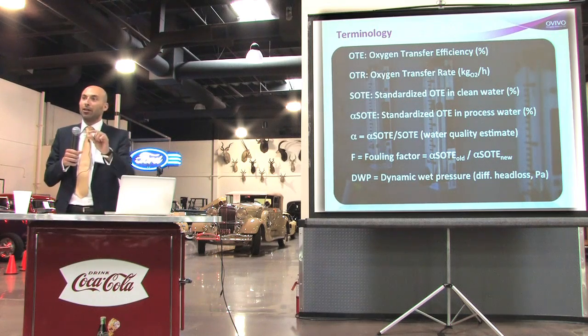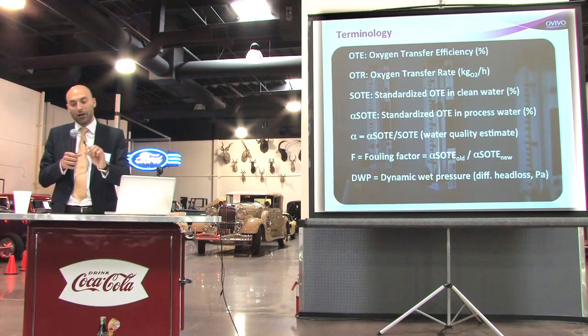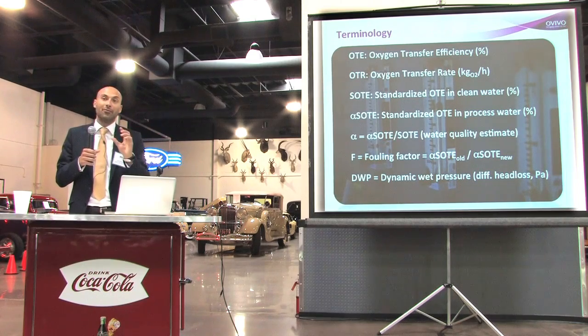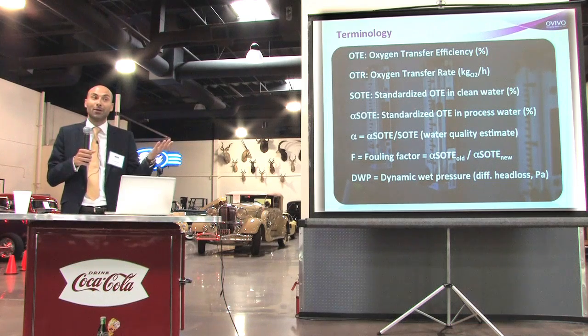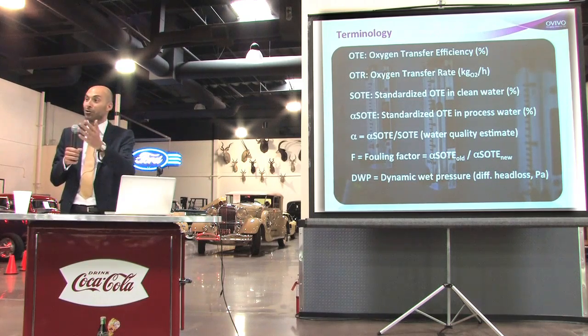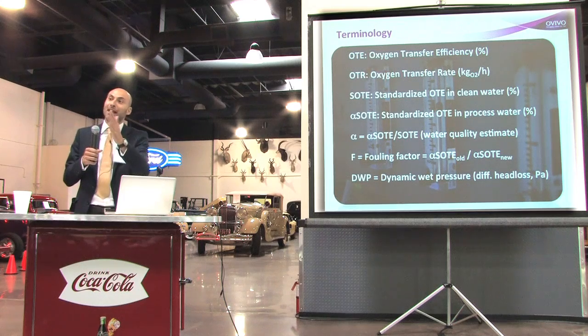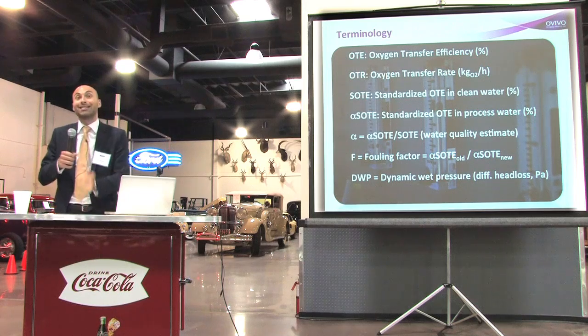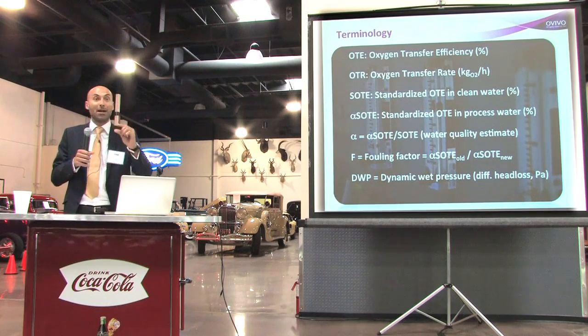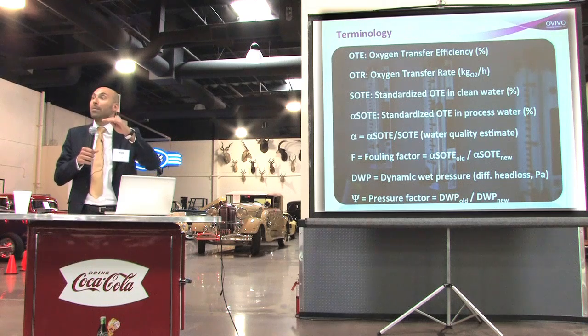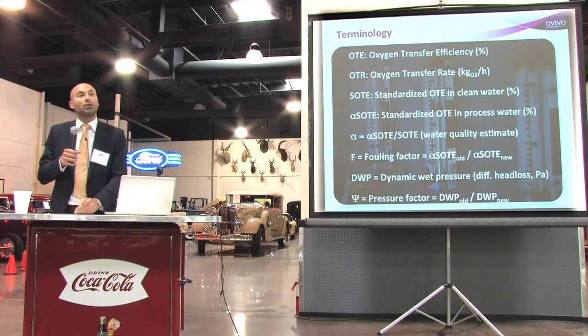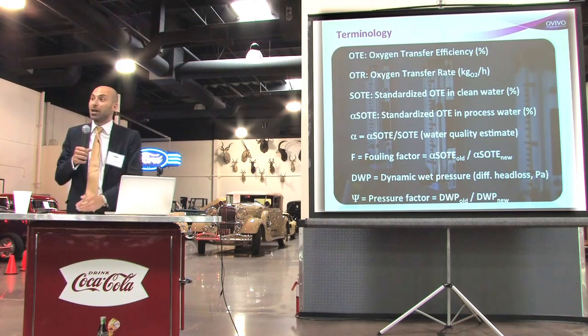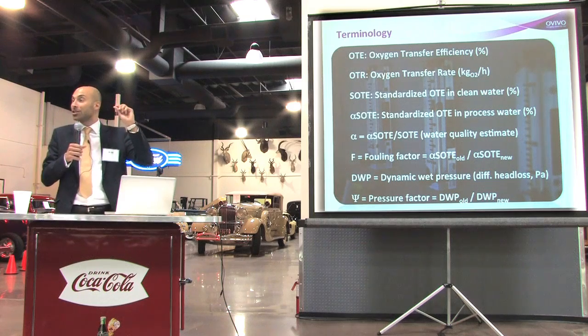The head loss across a diffuser is the dynamic wet pressure (DWP) — a critical parameter because blower selection depends first on discharge pressure, not size. Blowers cannot compress air, they blow it; if you don't have enough discharge pressure, the air won't come out. Over time, discharge pressure may creep up, potentially limiting the blower's ability to discharge air, so when sizing a blower today you must budget extra pressure to accommodate that future increase.